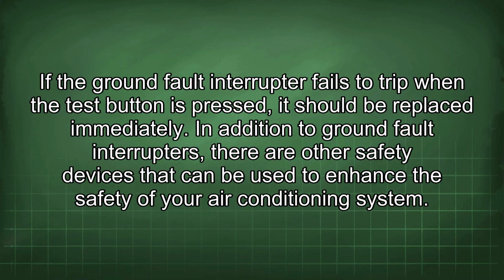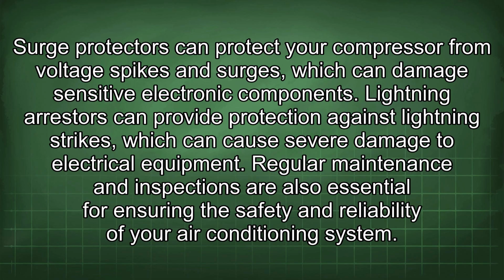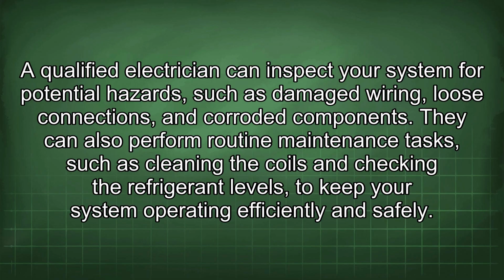In addition to ground fault interrupters, there are other safety devices that can be used to enhance the safety of your air conditioning system. Surge protectors can protect your compressor from voltage spikes and surges, which can damage sensitive electronic components. Lightning arresters can provide protection against lightning strikes, which can cause severe damage to electrical equipment. Regular maintenance and inspections are also essential for ensuring the safety and reliability of your air conditioning system. A qualified electrician can inspect your system for potential hazards, such as damaged wiring, loose connections, and corroded components. They can also perform routine maintenance tasks, such as cleaning the coils and checking the refrigerant levels to keep your system operating efficiently and safely.